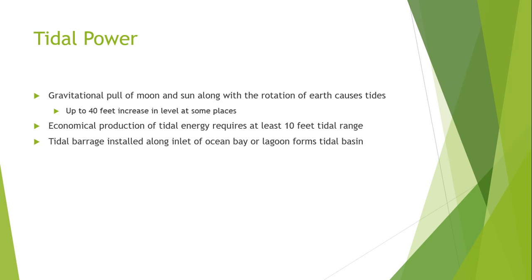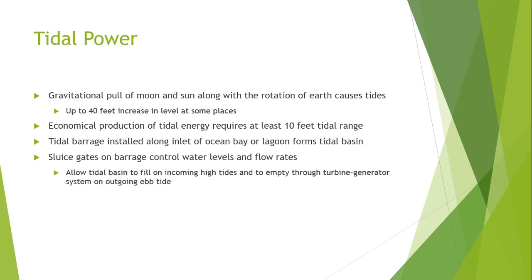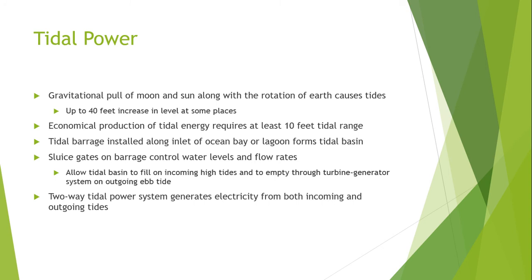A tidal barrage installed along the inlet of an ocean bay or lagoon forms a tidal basin. Sluice gates on the barrage control the water levels and flow rates. Using these gates we can control the filling of the basin, allowing it to fill from incoming high tides and emptying it through turbine generators. A two-way tidal power system generates electricity from both the incoming and outgoing tides.